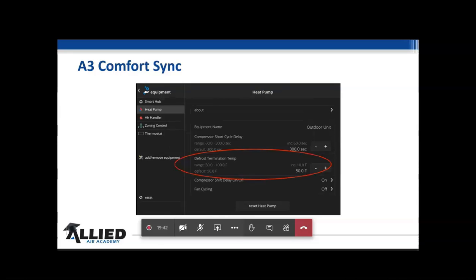And then you go to your heat pump right here. Your defrost termination temp, you can go from 50 to 100. The default is 50. So again, pay close attention, because when I put this A3 on my house, it did not pick up what I had previously set before. It stayed at the default. So we need to make sure they look at this and adjust it, because they can go 50, 60, 70, 80, 100. Make sure whatever region you're in, this gets adjusted, because that could be a callback where we're spending a lot of time trying to figure out what in the world could be causing this, and here it is right here. So another important thing to take a look at as we put these in. So that's the easy way to do it with the A3 comfort sync.